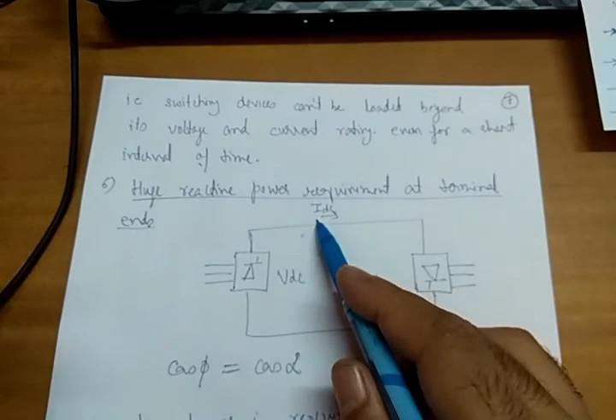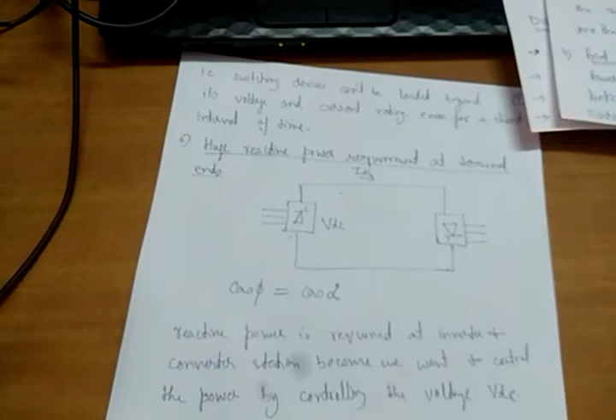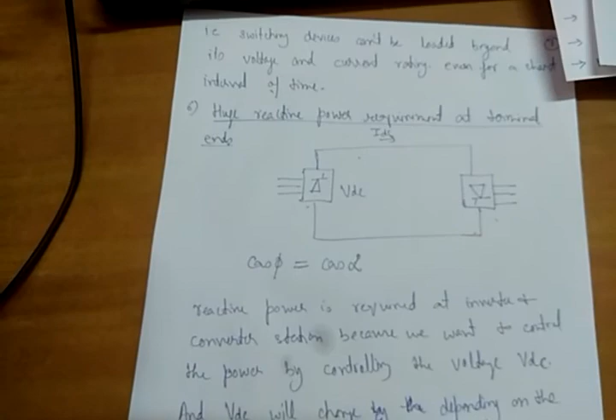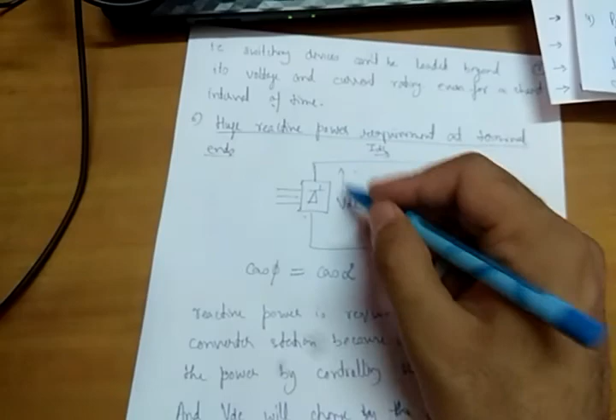So next is huge reactive power demand at the terminal system. Though no reactive power flows in this system, there is reactive power requirement at this station and at this station. It is because what is the power factor in power electronics? Power factor cos phi is nothing but cos alpha, where alpha is the delay angle. Reactive power is required at both the stations, because we want to control the power by controlling the voltage. By controlling the voltage, we can control the power. So for controlling the voltage, we need reactive power, and reactive power depends upon alpha.